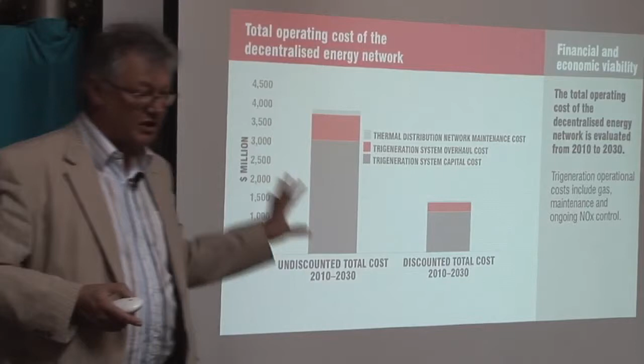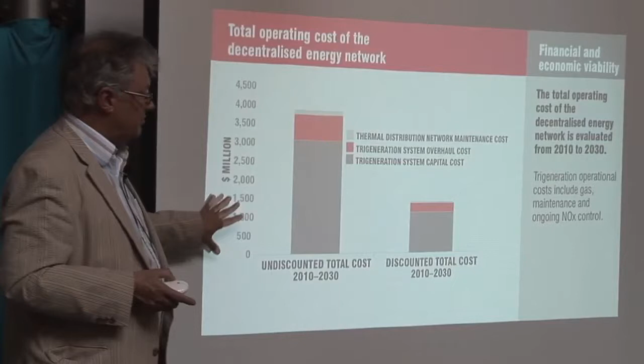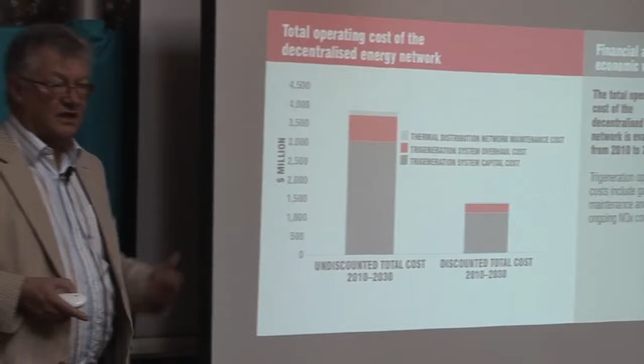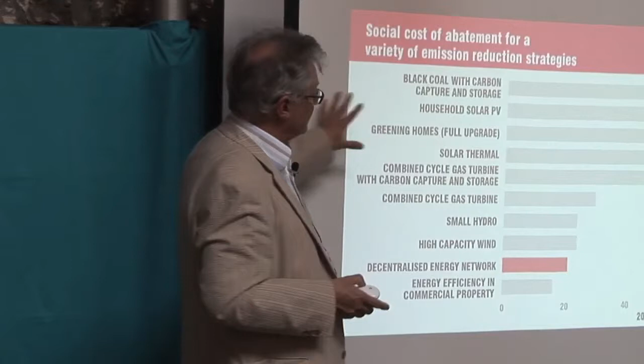We looked at operation and maintenance costs, the supply of gas, and the economics of this project will provide the tri-generation proponent an internal rate of return of between 10 and 20%, significantly higher than you would get with conventional power stations. In terms of cost of carbon abatement, in other words cost per tonne of reducing a tonne of carbon, energy efficiency is number 1, as you would expect.